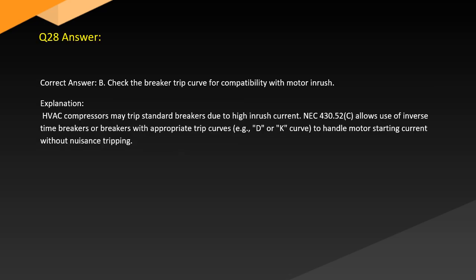Answer. Correct answer: B. Check the breaker trip curve for compatibility with motor inrush. Explanation. HVAC compressors may trip standard breakers due to high inrush current. NEC 430.52(C) allows use of inverse time breakers or breakers with appropriate trip curves, such as D or K curve, to handle motor starting current without nuisance tripping.